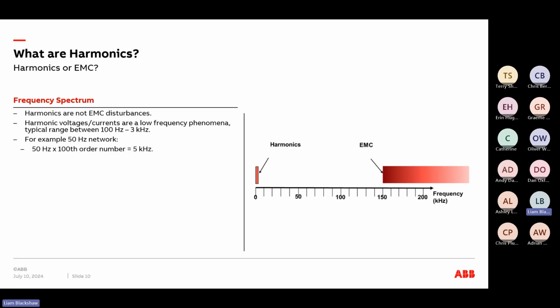And obviously when I say EMC, we're looking at electromagnetic compatibility, and those kinds of standards address both interference and harmonics to a certain extent. So as an example, we mentioned things like the order of things. If we looked at a 50 hertz network, for example, and I wanted to look at the 5 kilohertz signal, that would be what we class as the 100th order, because it's 50 times 100, which is 5 kilohertz. If we wanted to look at the 5th order of harmonics, we multiply those two together, and that gives us 250 hertz, and so forth.